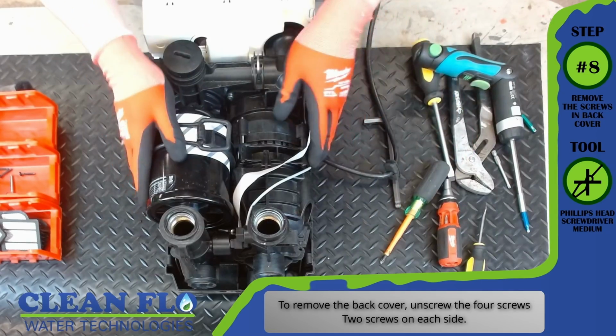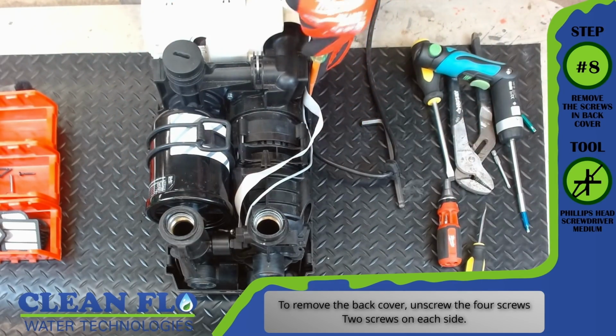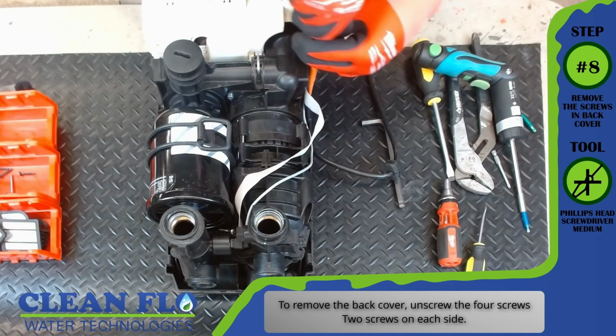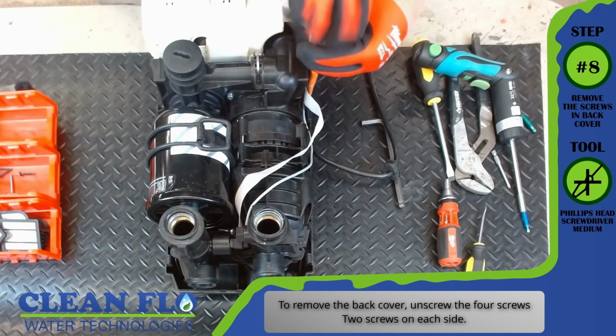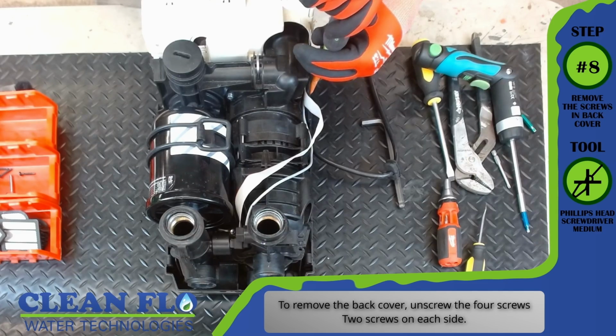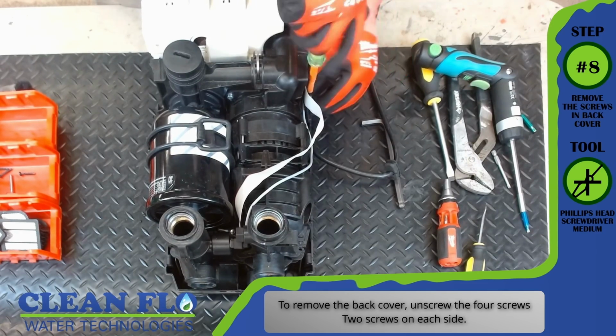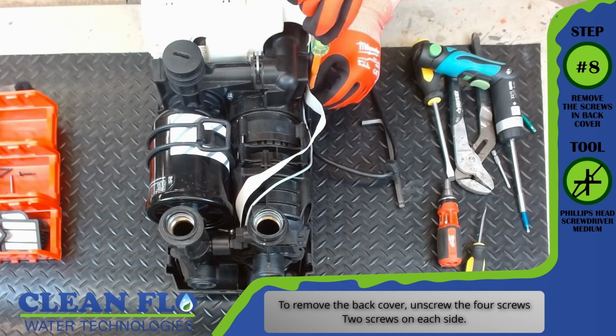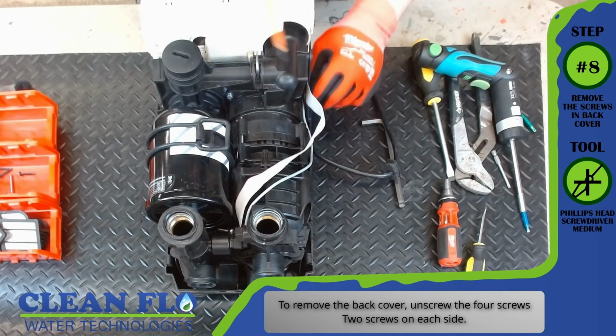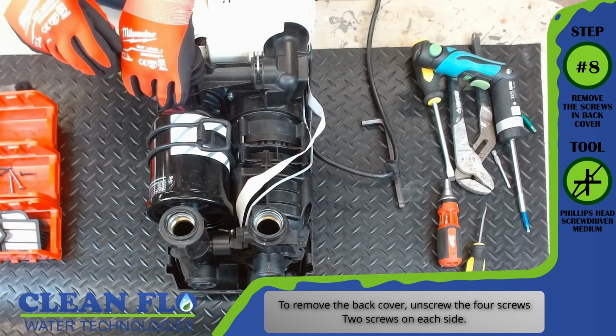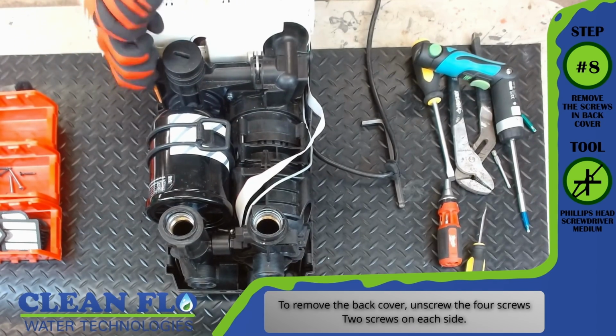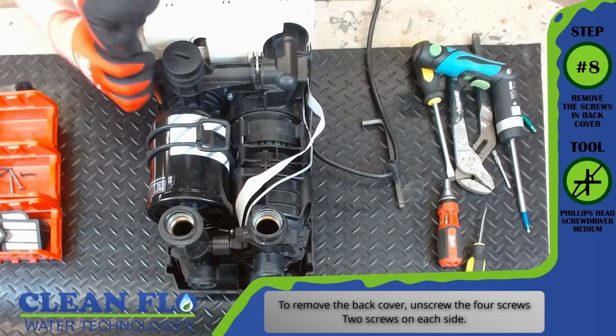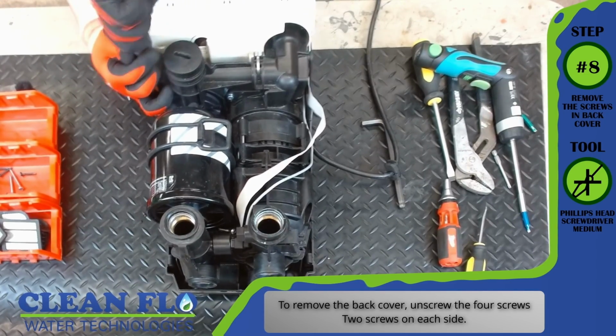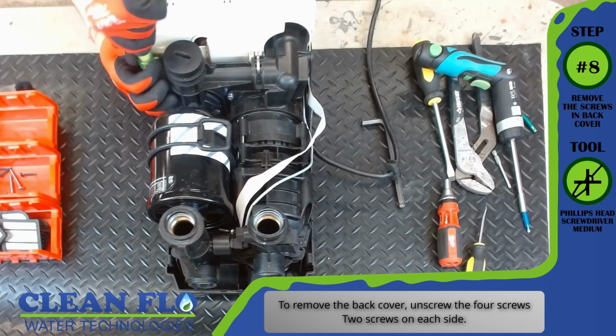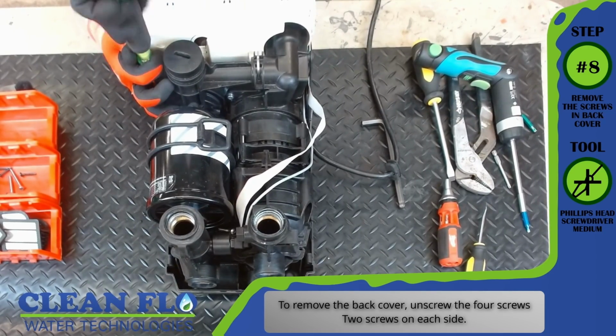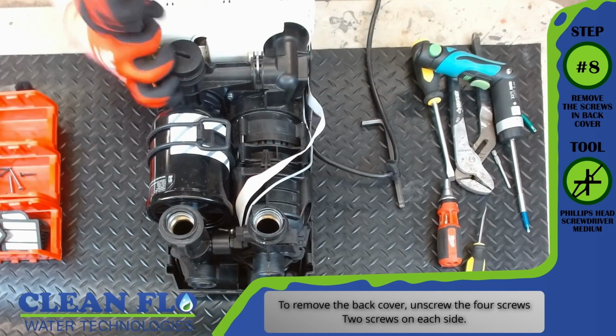Now, one of my screws did fall between the pump assembly, and what I will do, prior to moving to the next step, is make sure I grab that screw or tip it out and put it into its respective container. Now, with these 4 screws removed, the whole bottom cover will be free, and we can actually start disassembling the pump mechanical components.